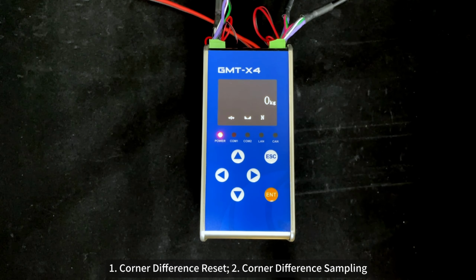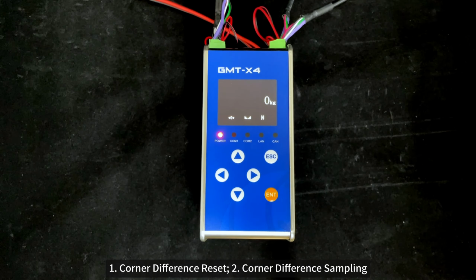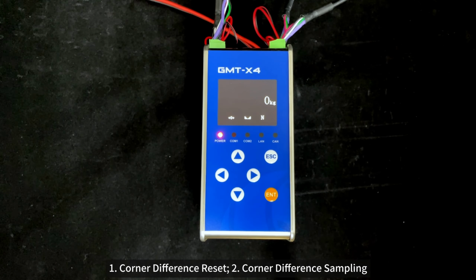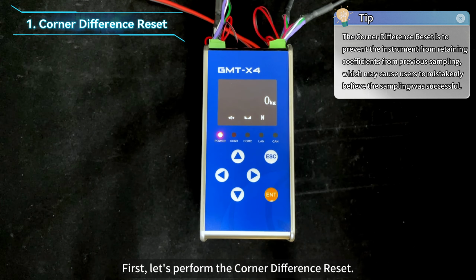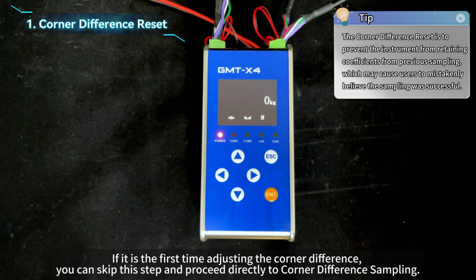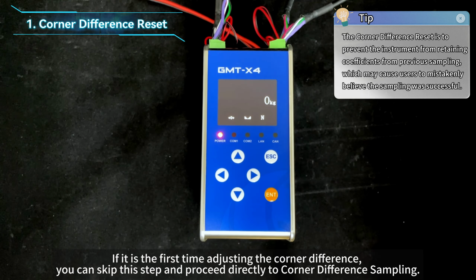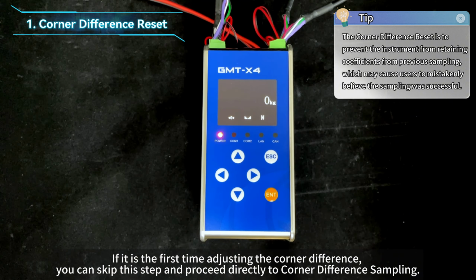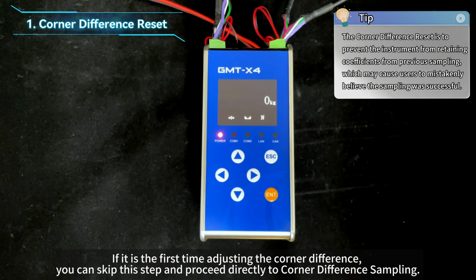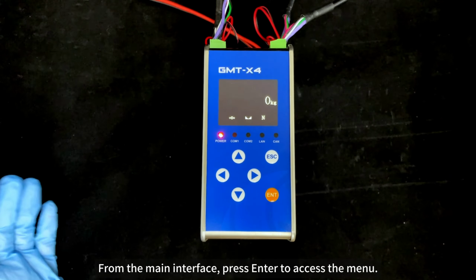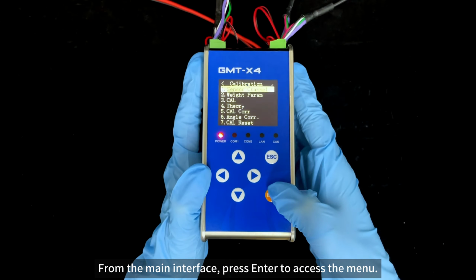There are 2 steps for corner difference adjustment. 1. Corner difference reset. 2. Corner difference sampling. First, let's perform the corner difference reset. If it is the first time adjusting the corner difference, you can skip this step and proceed directly to corner difference sampling. From the main interface, press Enter to access the menu.